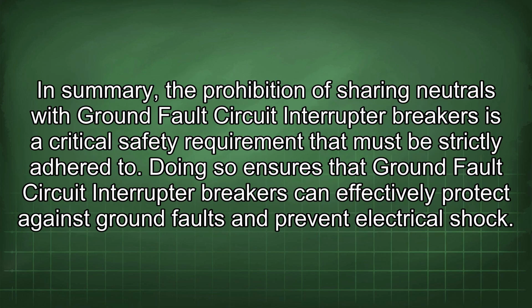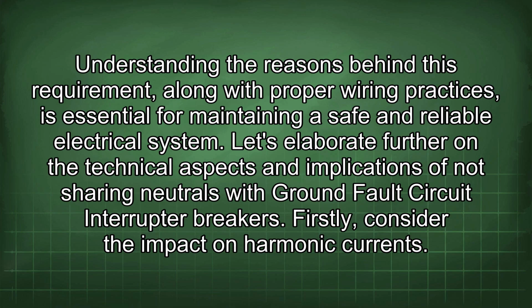In summary, the prohibition of sharing neutrals with ground fault circuit interrupter breakers is a critical safety requirement that must be strictly adhered to. Doing so ensures that ground fault circuit interrupter breakers can effectively protect against ground faults and prevent electrical shock. Understanding the reasons behind this requirement, along with proper wiring practices, is essential for maintaining a safe and reliable electrical system. Let's elaborate further on the technical aspects and implications of not sharing neutrals with ground fault circuit interrupter breakers.